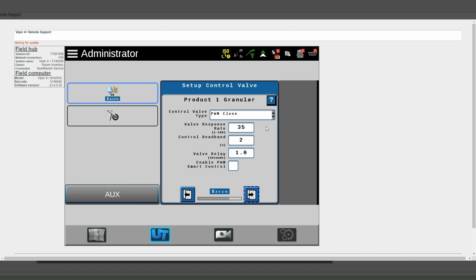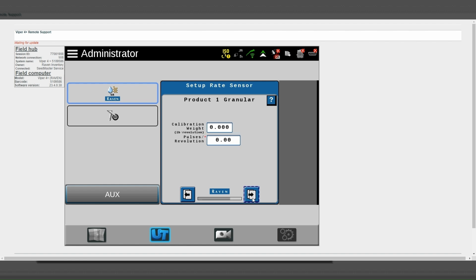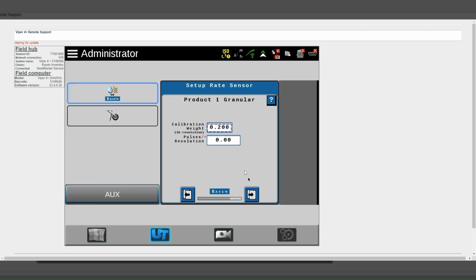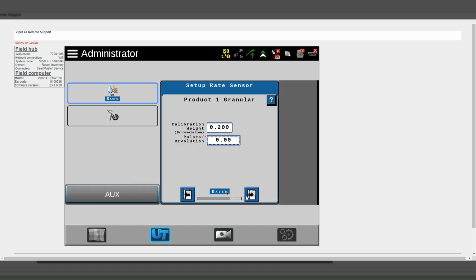The valve response should be defaulted to 35, the control deadband to 2, a valve delay of 1 second, and enable PWM smart control should not be checked. Your coil frequency will be 65 Hz, your PWM high limit will be 100, PWM low limit will be 1, and startup will be 0. Your calibration weight for the first product is a small seeds tank, and therefore can be set to 0.2, and the pulses per revolution for electric meter setups is 275.2.